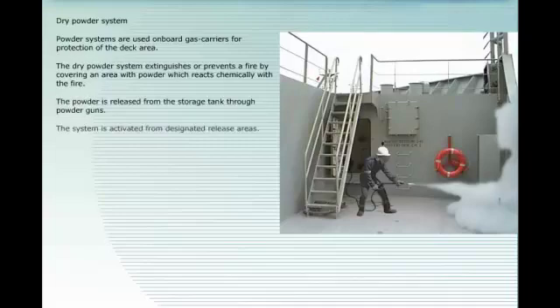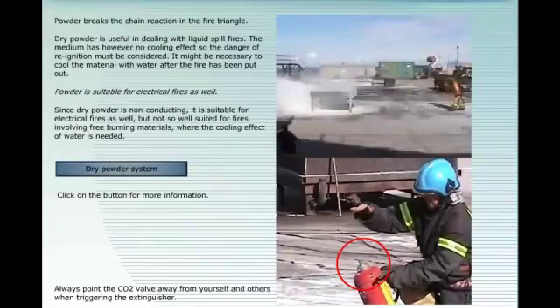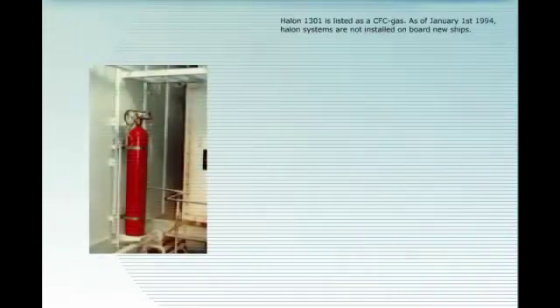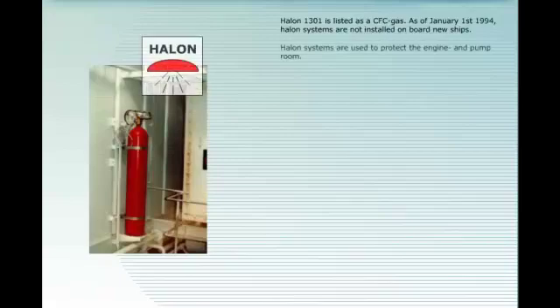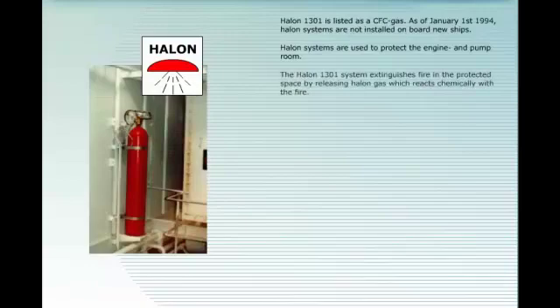Halon 1301 is listed as a CFC gas. As of January 1, 1994, halon systems are not installed onboard new ships. Halon systems are used to protect the engine and pump room. The halon 1301 system extinguishes fire in the protected space by releasing halon gas, which reacts chemically with the fire. It is activated from designated release areas.